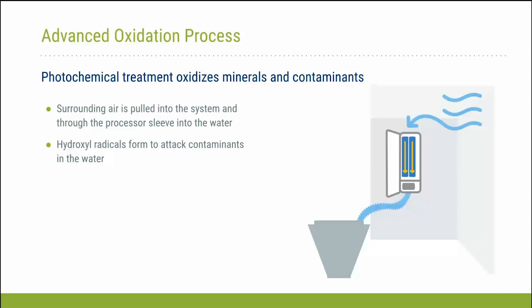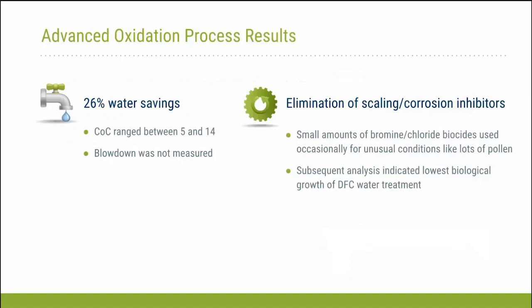The savings we saw on this one was 26% water savings. We did not see as significant an improvement in cycles of concentration - I think the average was about 11. That being said, even though they operated at a lower cycles of concentration versus the other technologies, it did still save a significant amount of water.